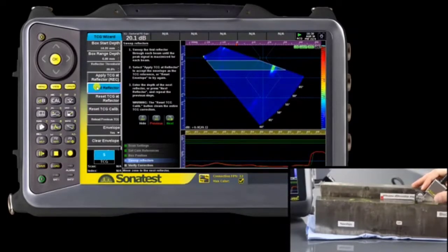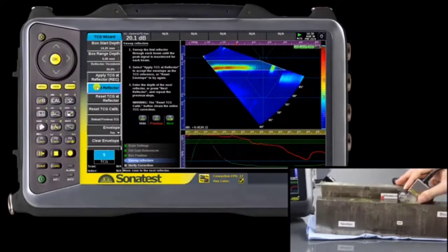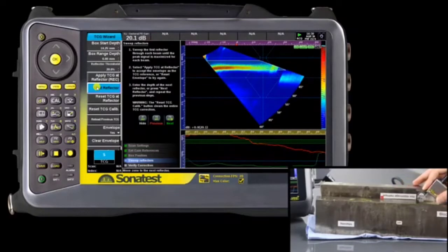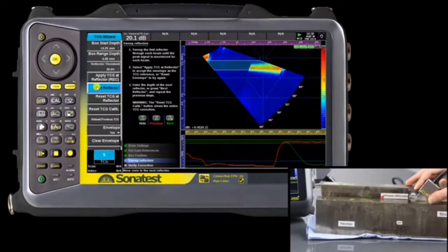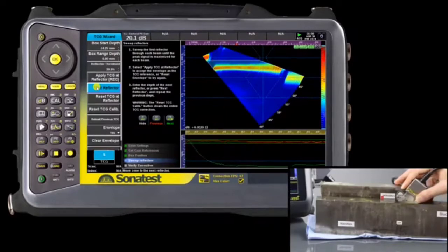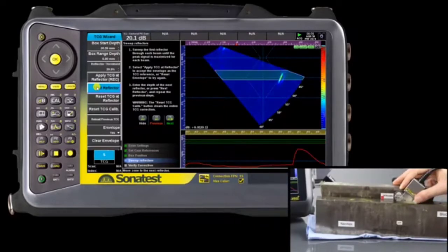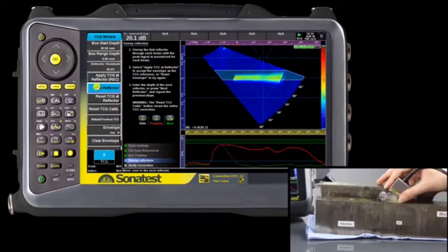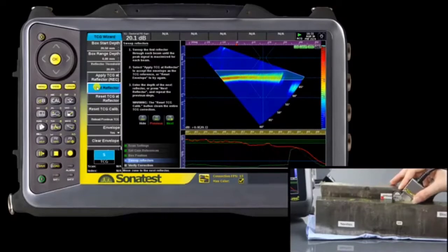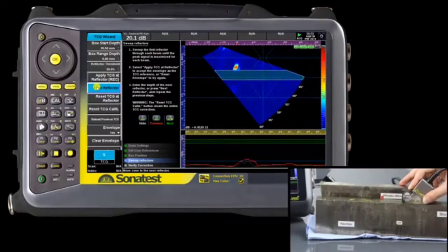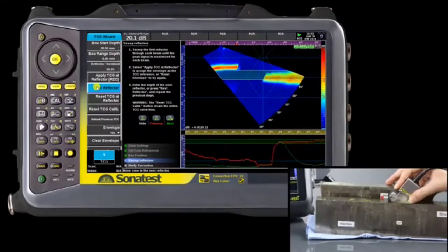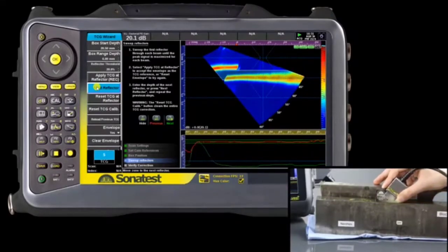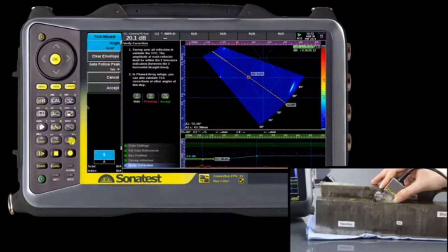Once the signal is within the tolerance, we can do the next reflector. Now that the coupling and the probe relative positions are optimised, the second and third reflector should be easier. The second and third reflector only need one iteration to enter within the TCG curve tolerance.